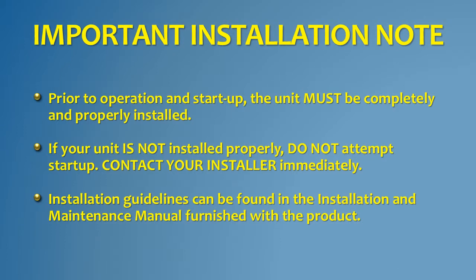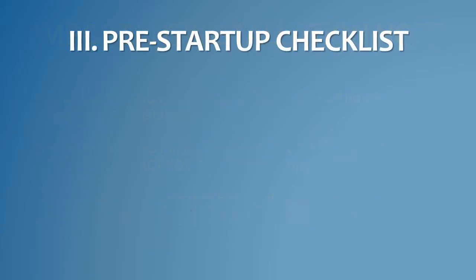Important: before starting the water heater, ensure the unit is installed completely and properly. If your unit is not installed properly, do not attempt startup. Contact your installer immediately.